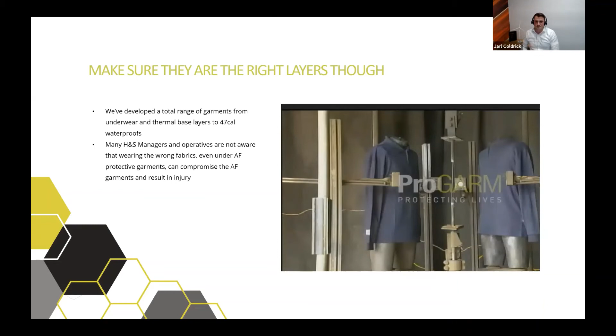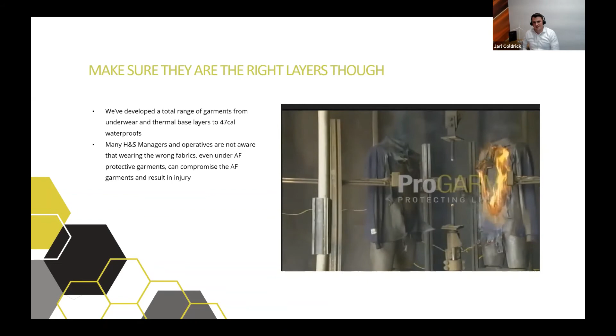This is a very interesting scenario where people might think they're protected wearing an arc flash outer layer, but even 100% cotton with a high melting point has ignited in this event. So whether it's 100% cotton, polycotton, or nylon, we don't recommend it be worn underneath arc flash clothing.